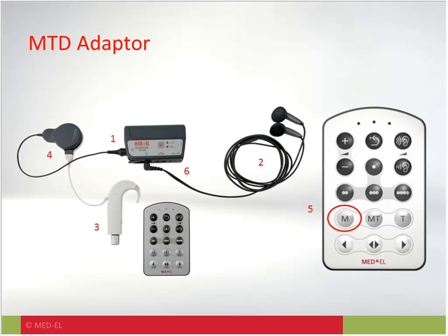So you can follow along with the numbers. So number 1, you connect the SONNET MTD adapter, which is that long cable thing, to the microphone test device, which is that big gray rectangle in the middle. So you connect the two together at that number 1 point. And then number 2, you connect the headphones to the microphone test device. So that's what an adult would use to listen to evaluate the microphone. And then number 3, you remove the SONNET audio processor from the patient's head, and you place the SONNET coil, number 4, on the flat side of the MTD adapter. So that's where you see at number 4, that adapter connects to the child's coil.